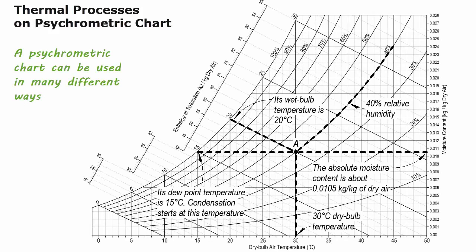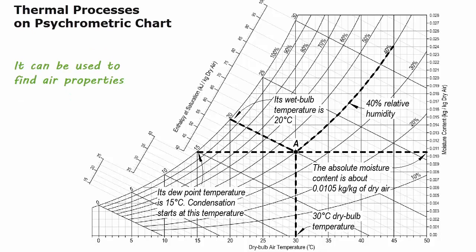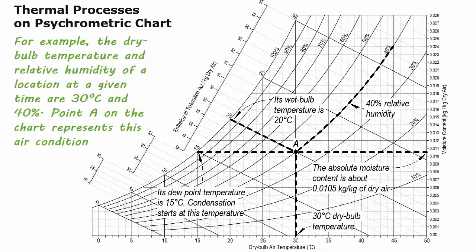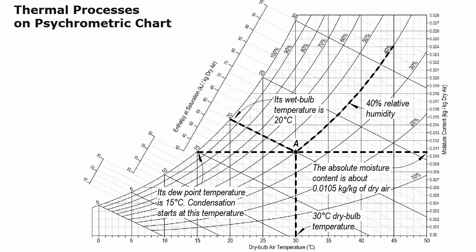A psychrometric chart can be used in many different ways, including to find air properties. For example, the dry bulb temperature and relative humidity of a location at a given time are 30 degrees C and 40%. Point A on the chart represents this air condition, and from this point all other air properties can be found.